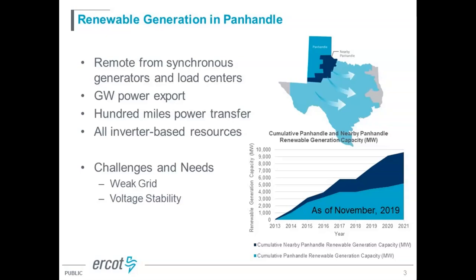Synchronous machines and load centers are far away from this region. So obviously, all the output will be exported out of this region. It's really a gigawatt-level power export out of the Panhandle region. On top of that, similar to the previous presentation, the power needs to be transferred to a load center. In this case, it's a 100-mile power transfer: a gigawatt of power through a 100-mile transfer from the inverter-based concentrated area to the load center in ERCOT.